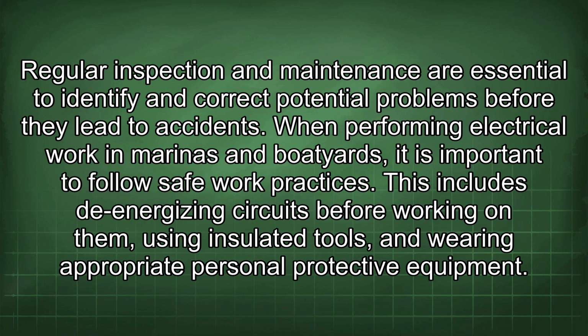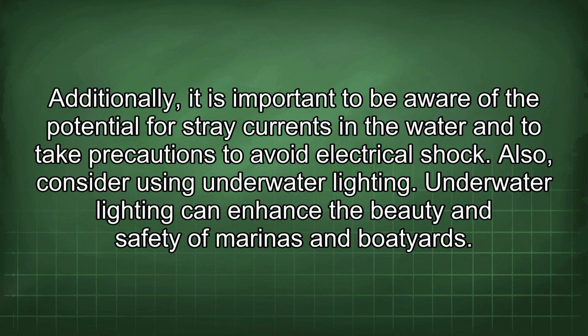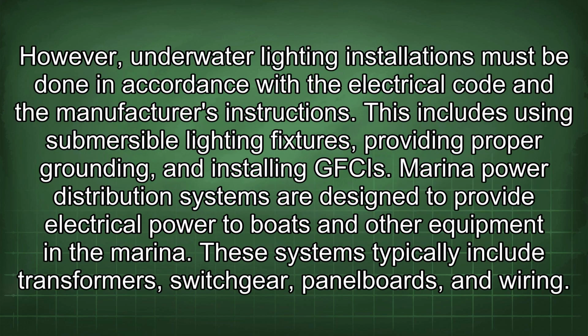When performing electrical work in marinas and boatyards, it is important to follow safe work practices. This includes de-energizing circuits before working on them, using insulated tools, and wearing appropriate personal protective equipment. Additionally, it is important to be aware of the potential for stray currents in the water and to take precautions to avoid electrical shock. Also, consider using underwater lighting. Underwater lighting can enhance the beauty and safety of marinas and boatyards. However, underwater lighting installations must be done in accordance with the electrical code and the manufacturer's instructions. This includes using submersible lighting fixtures, providing proper grounding, and installing GFCIs.